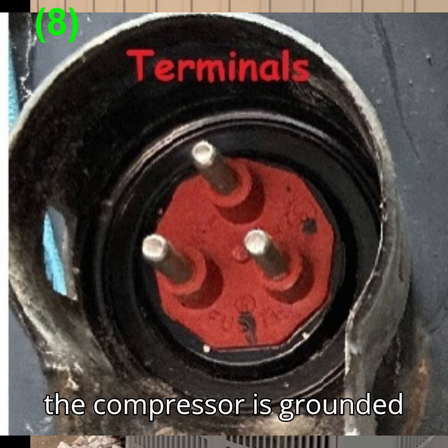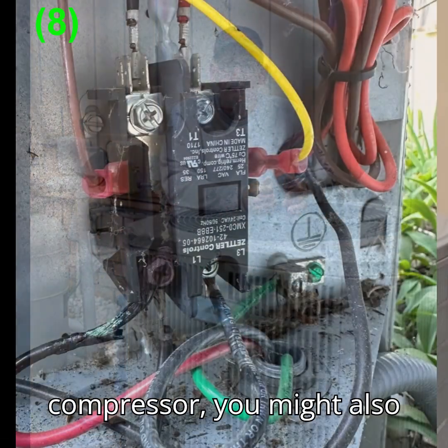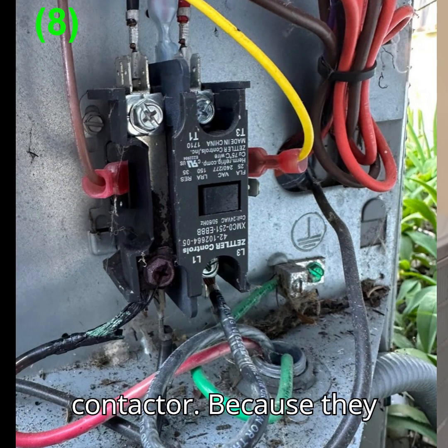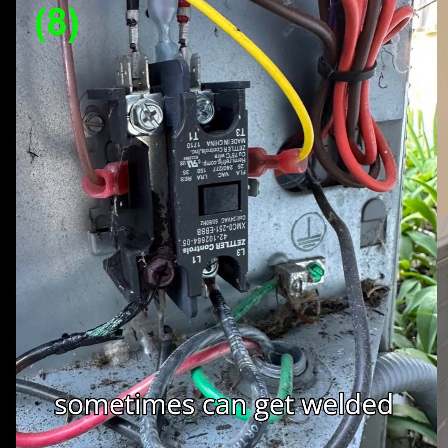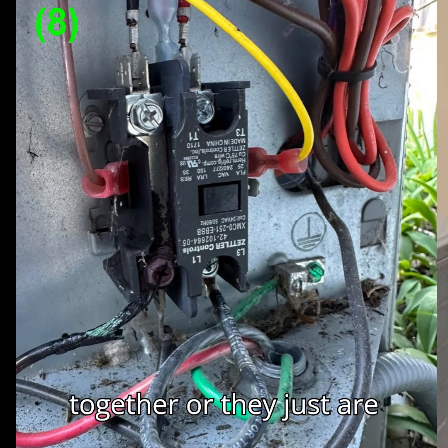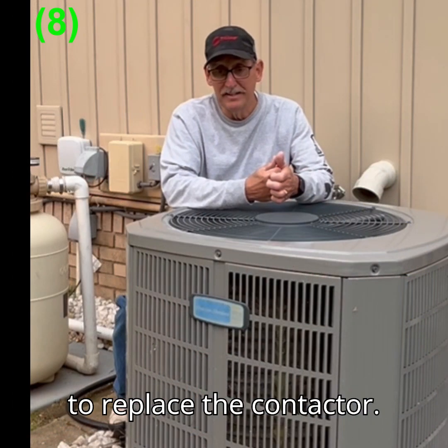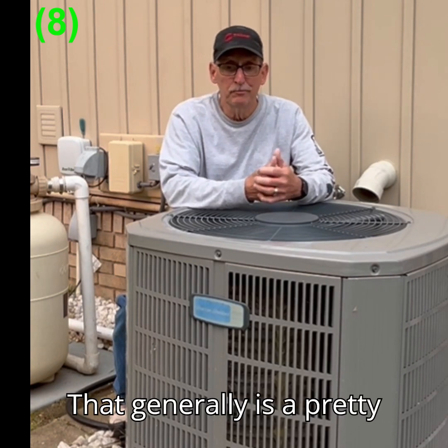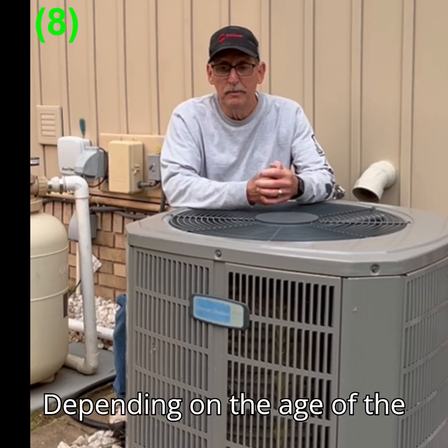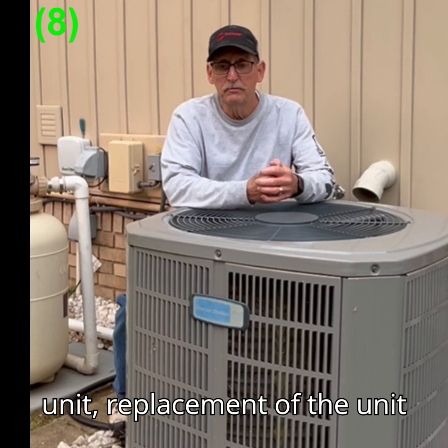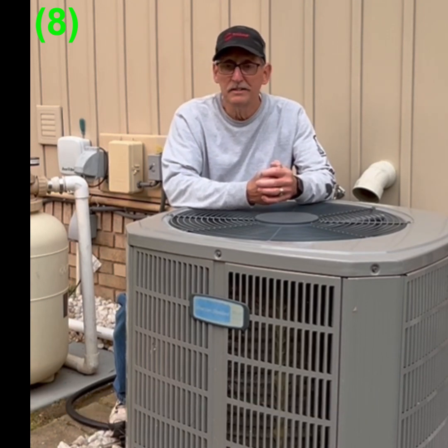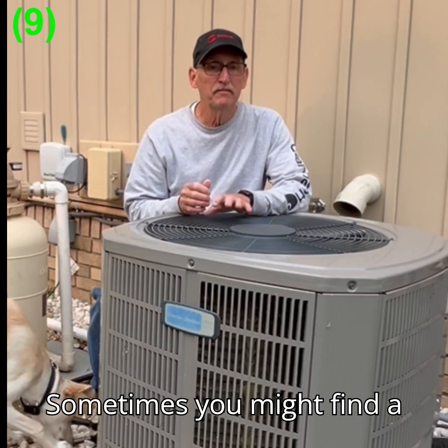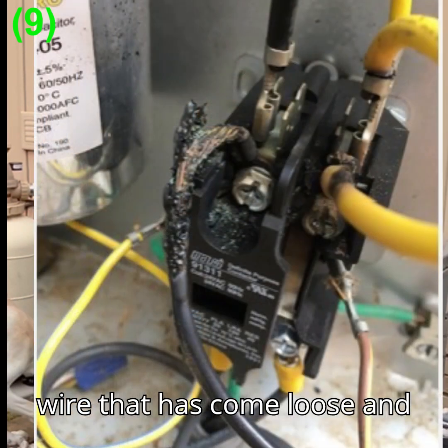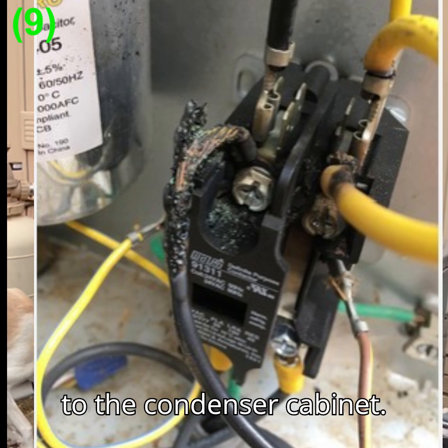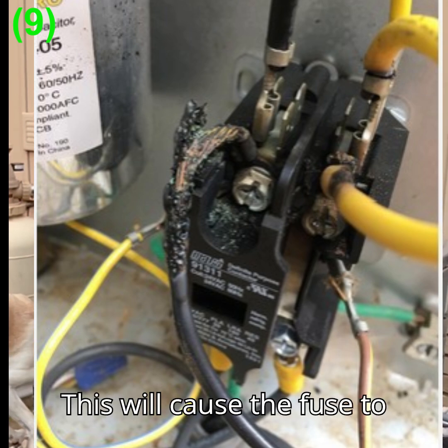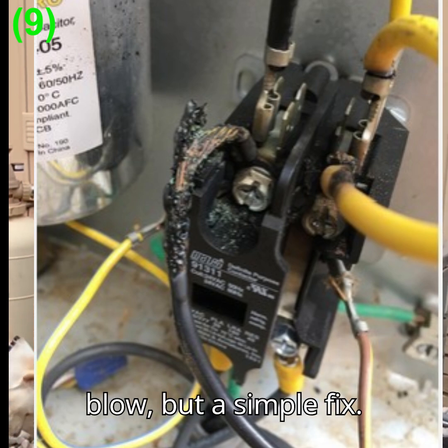If the compressor is grounded and you need to change the compressor, you might also have to change the compressor contactor, because they sometimes can get welded together or they just are abused. It's not a bad idea to replace the contactor. That generally is a pretty expensive service call. Depending on the age of the unit, replacement of the unit might be the best choice. Sometimes you might find a wire that has come loose and the contactor has shorted out to the condenser cabinet. This will cause the fuse to blow, but it's a simple fix.